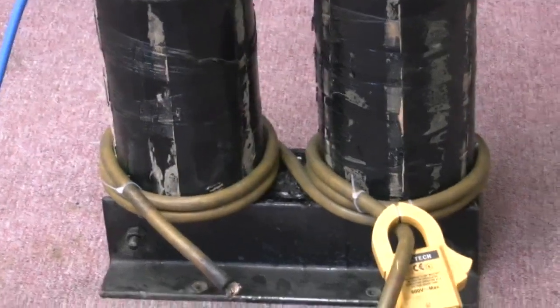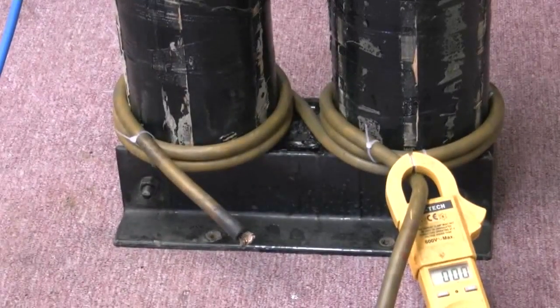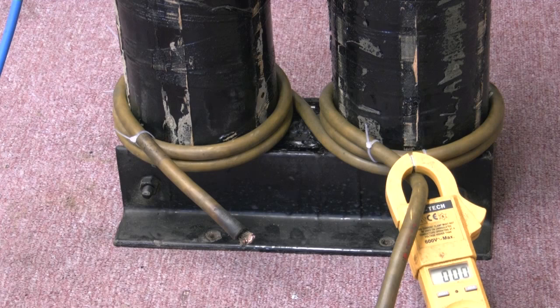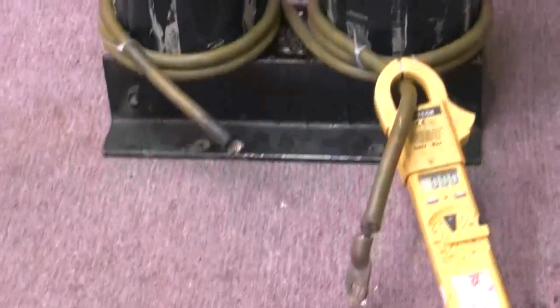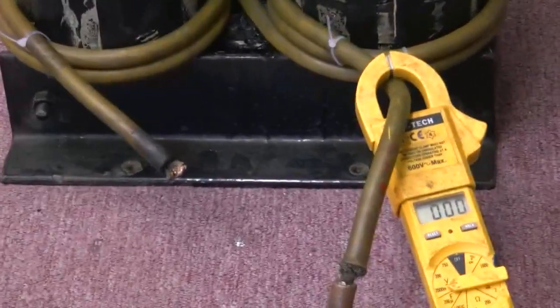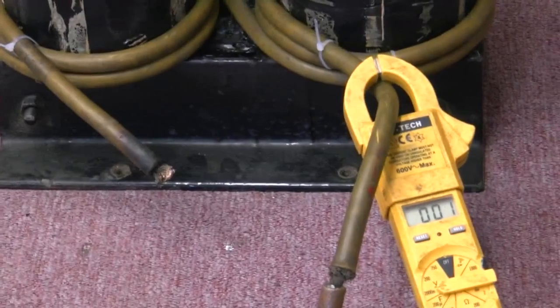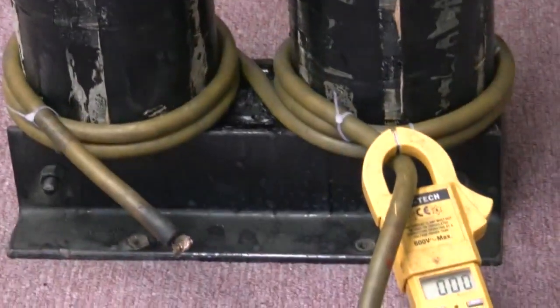I've just put some welding cable on there, which is only 35mm, just to see how many amps we can get and to check the phasing. Obviously I'm going to put some cable on there which is 10 times that diameter, so we're going to have quite a bit of current. Let's see if I can sort those out and get a current reading with just those.